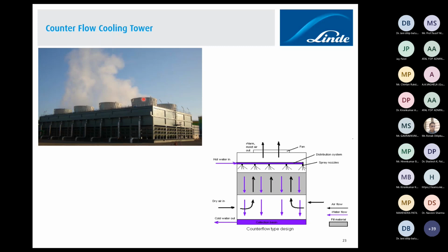And sometimes, down the line in the process there are many heat exchangers, and every heat exchanger has a hidden margin of 5 to 10% on the hydraulic part as well as on the temperature variation part. So instead of 32, if it sometimes increases to 32.5, I am sure those exchangers are not going to be impacted. So before deciding on the range and flow, we always consult the process engineers associated with the core processes, who designed the heat exchangers, about what margin is available. That's the reason we usually do not build an over margin or double margin in the cooling tower. If they have considered sufficient margin on hydraulic and temperature parts, then we usually do not offer a variable pitch fan or a VFD, variable frequency drive, on the motors. We simply offer an ordinary fan where on and off operation suffices.